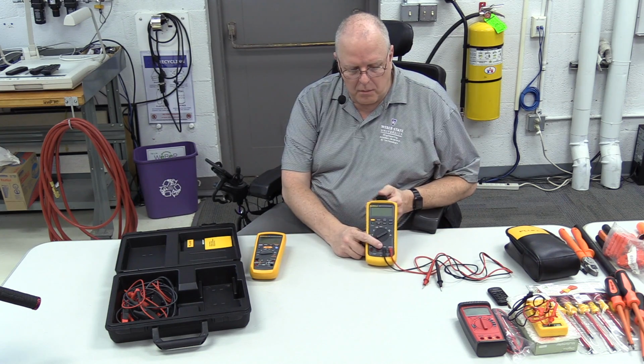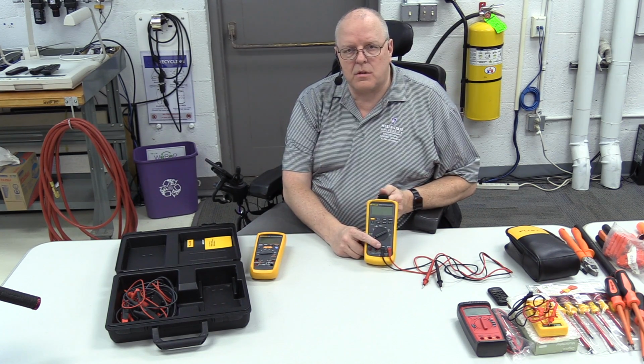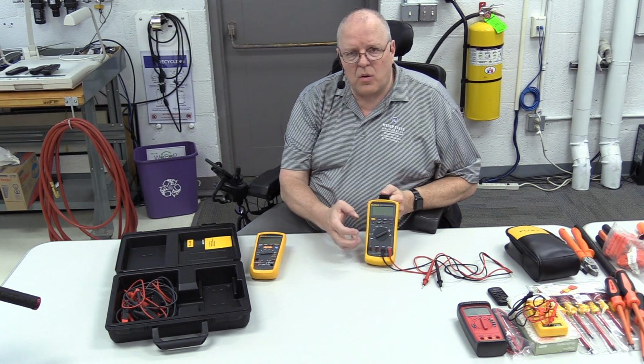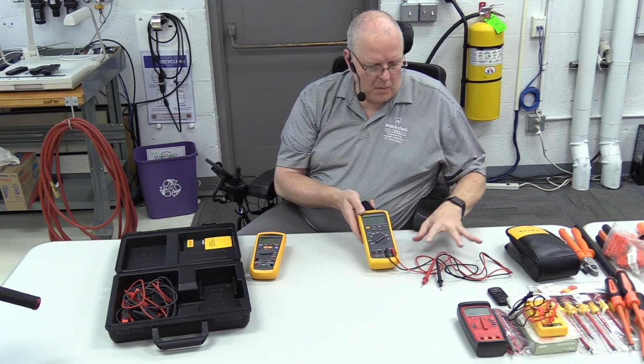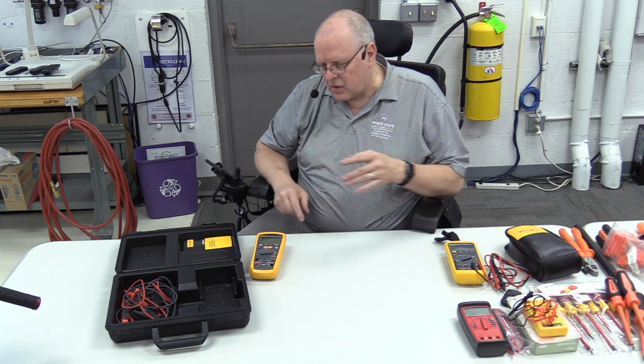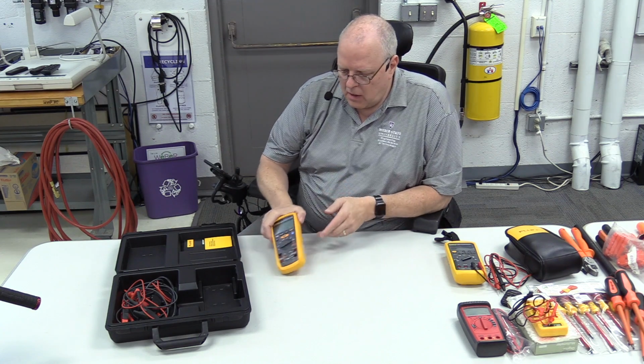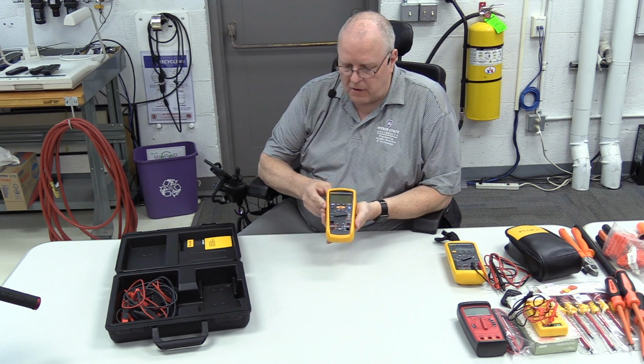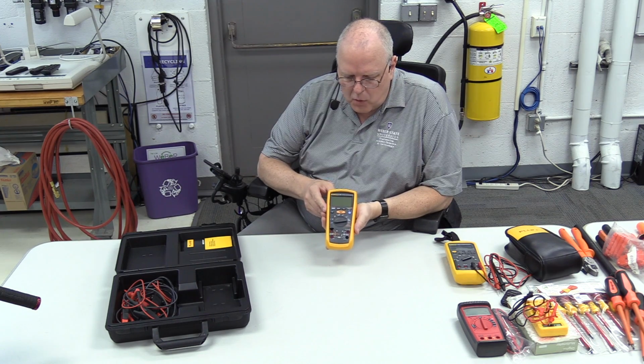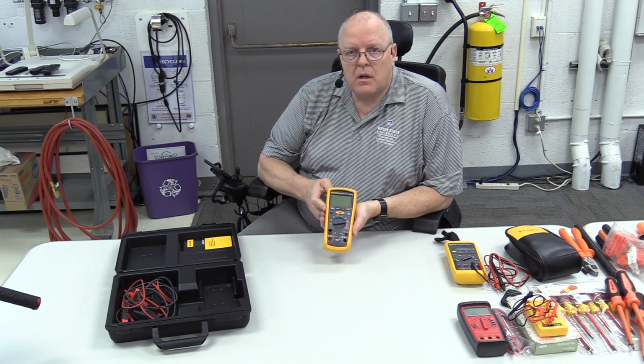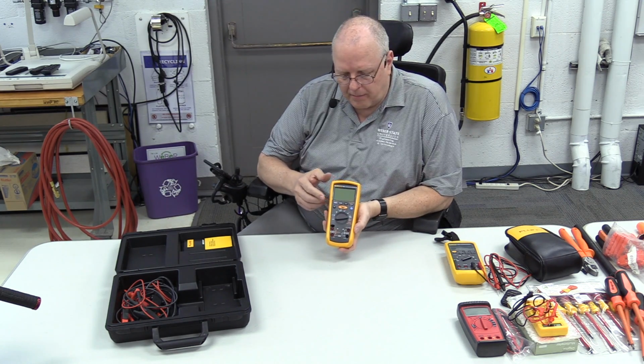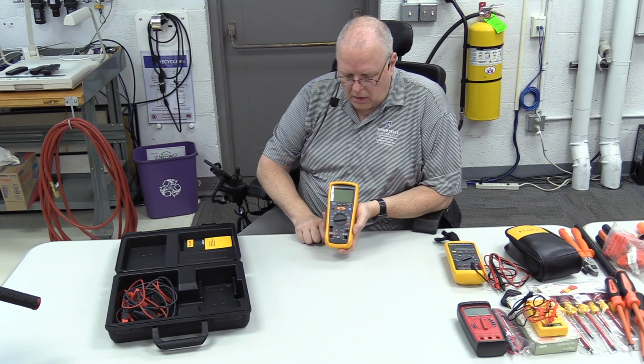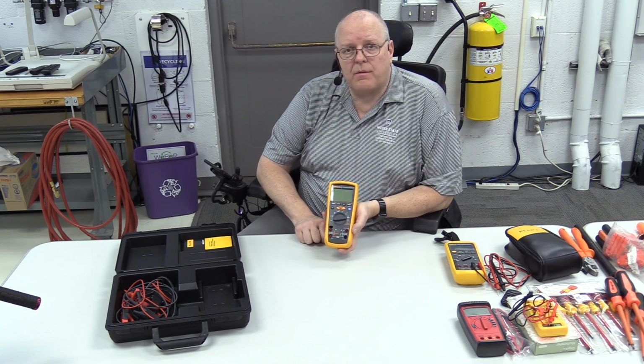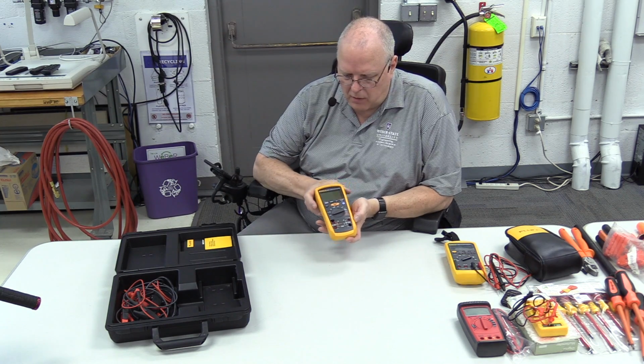The voltage that the Fluke 87 meter uses to measure resistance isn't anywhere near the voltage that is normally used in those circuits, and so it doesn't have enough power to measure that resistance accurately. But this meter, the Fluke 1587, can apply up to 1000 volts while measuring resistance to check for short circuits in the stator windings of a hybrid or electric vehicle.